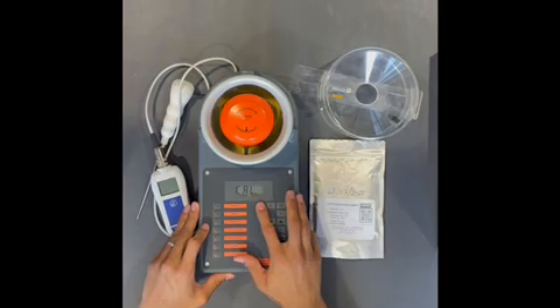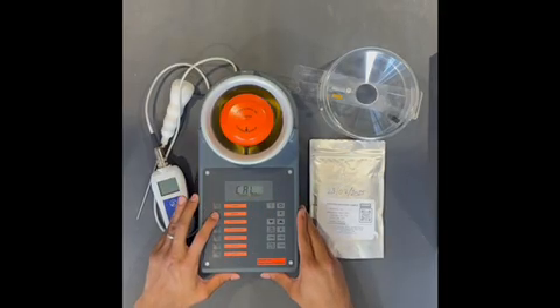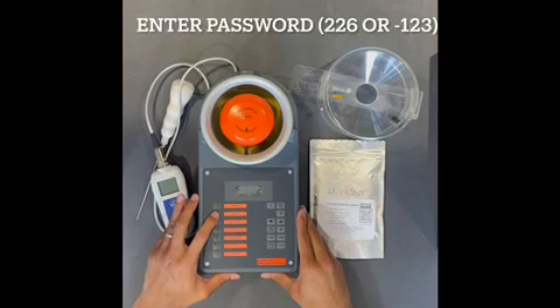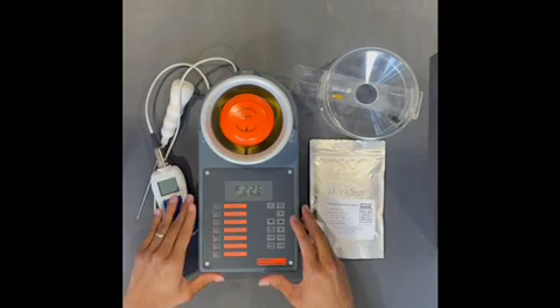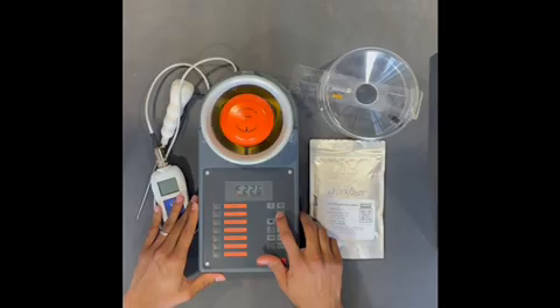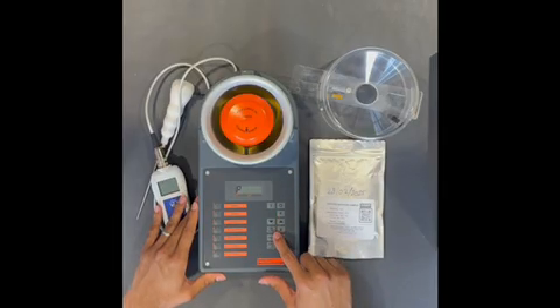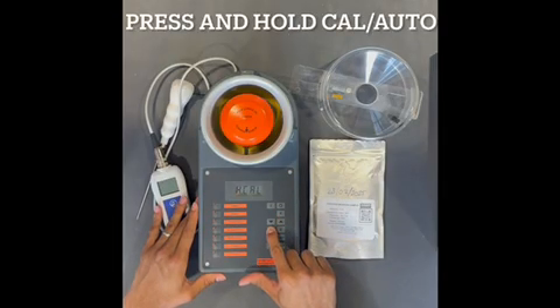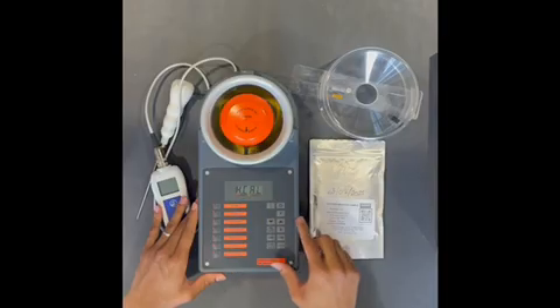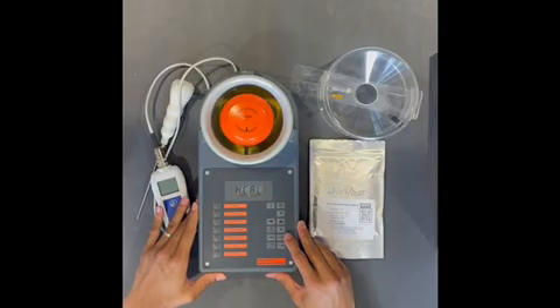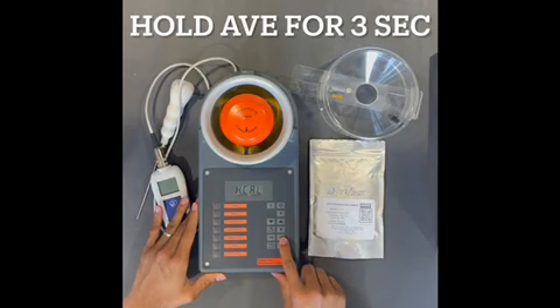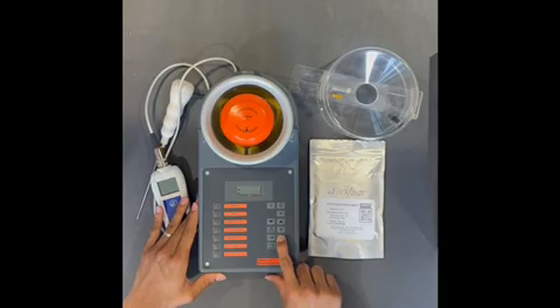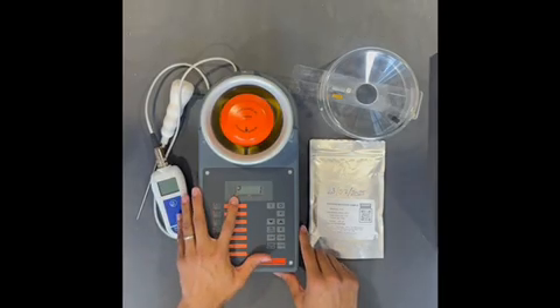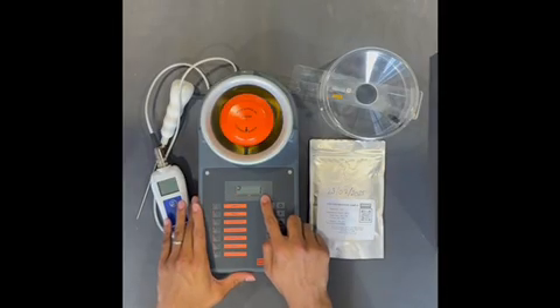The word Cal will show up on the screen, where we then want to go ahead and press 226 as the password and go ahead and press P. We then want to go ahead and hold down Cal Auto again for about 3 seconds until we see HCal. We then want to go ahead and hold down average for 3 seconds until we get an upside down C with a number 1.